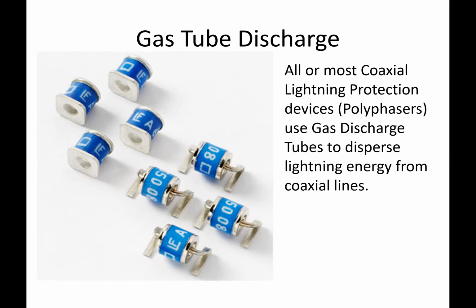What happens if you don't have a maintenance cycle or don't replace your gas tube discharge devices inside your coaxial protection devices? The short answer is, if it sustains a voltage hit, you could consume the gas inside, or completely damage the device, which then no longer provides any protection for the coax it's serving. So you have no parallel path to ground, in other words.